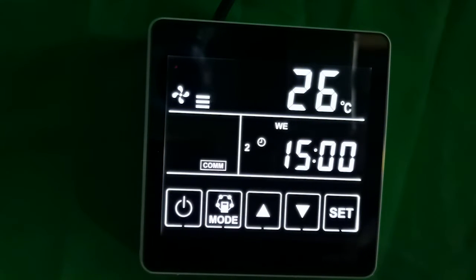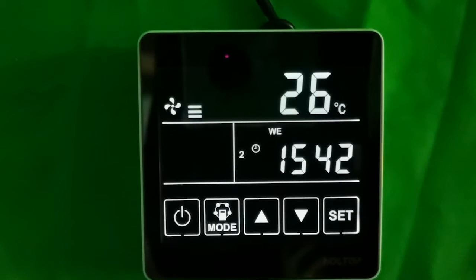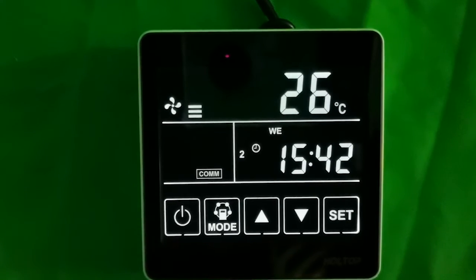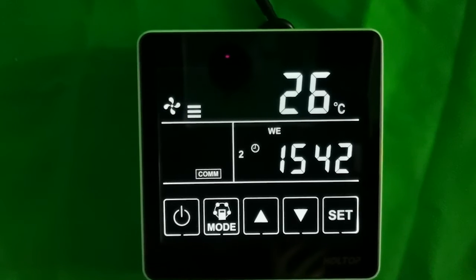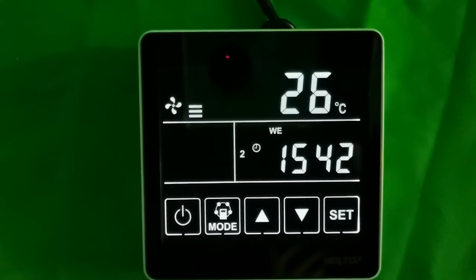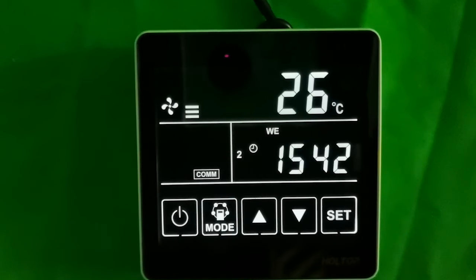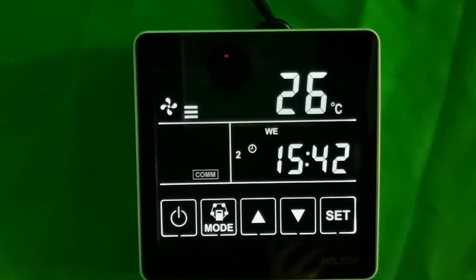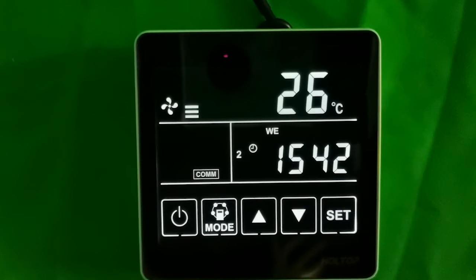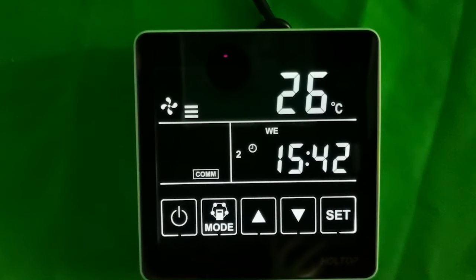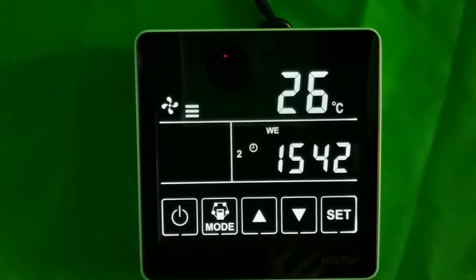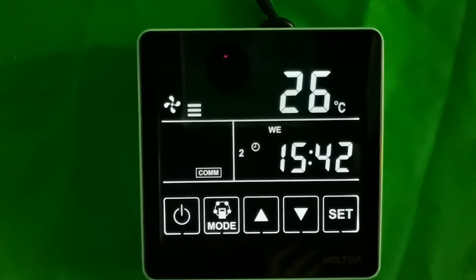Now we finish the time setting — it is very easy to handle. Our black cool controller supports weekly time setting. If we want the fan to run at a certain speed at a certain time, we can use the weekly timer function. Our system supports four periods per day, seven days per week. Under every period, the user can set a fan speed, and the ventilator will automatically change to that fan speed.